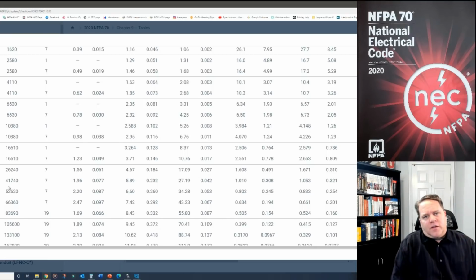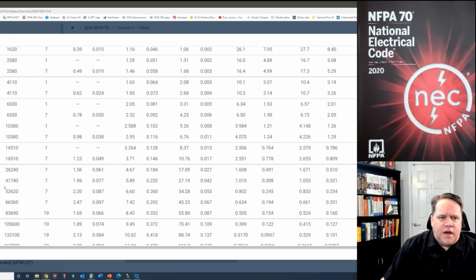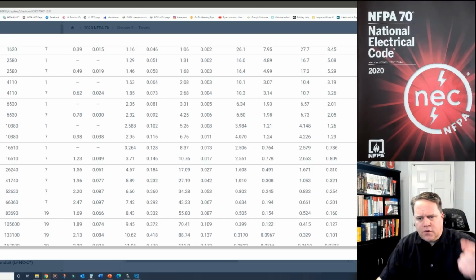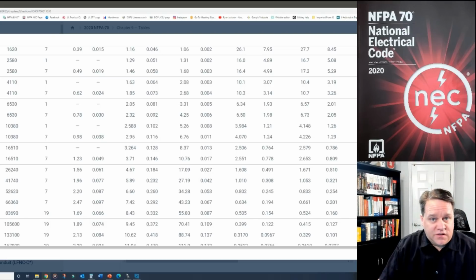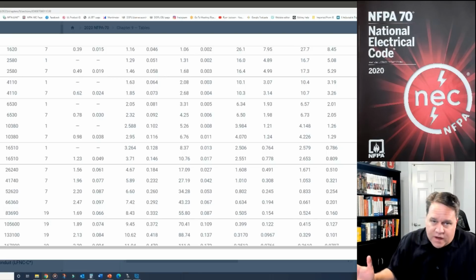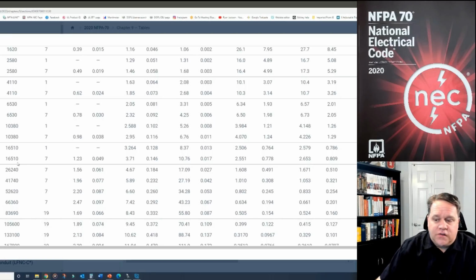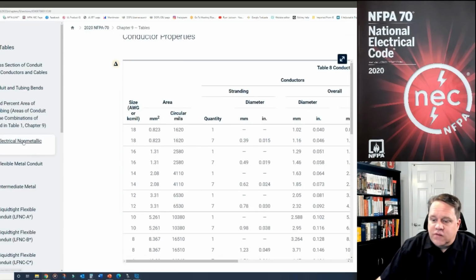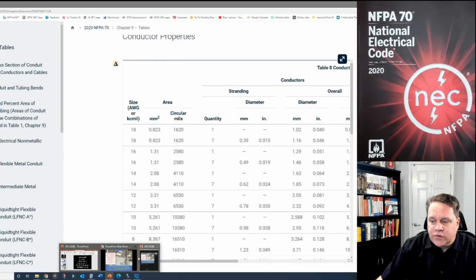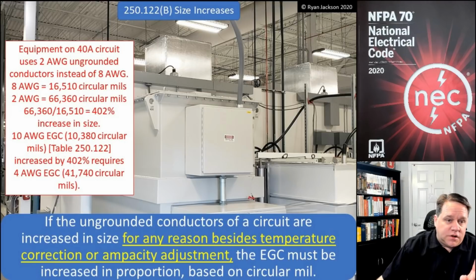The mistake that a lot of people will make is they'll say, okay, well, I increased from 8 gauge to 2 gauge, and that's an increase of 1, 2, 3, 4 conductor sizes. So I need to increase the equipment ground by 1, 2, 3, 4 conductor sizes. That's not a proportionate increase. Proportion means mathematically. So we do have to do this exercise anytime I increase the size of the ungrounded conductors for voltage drop. But I want to be clear on this.